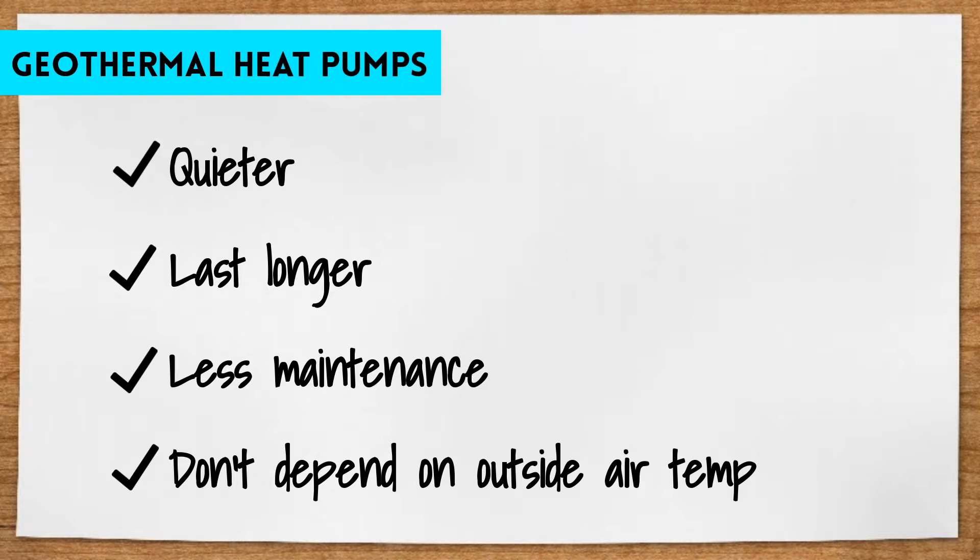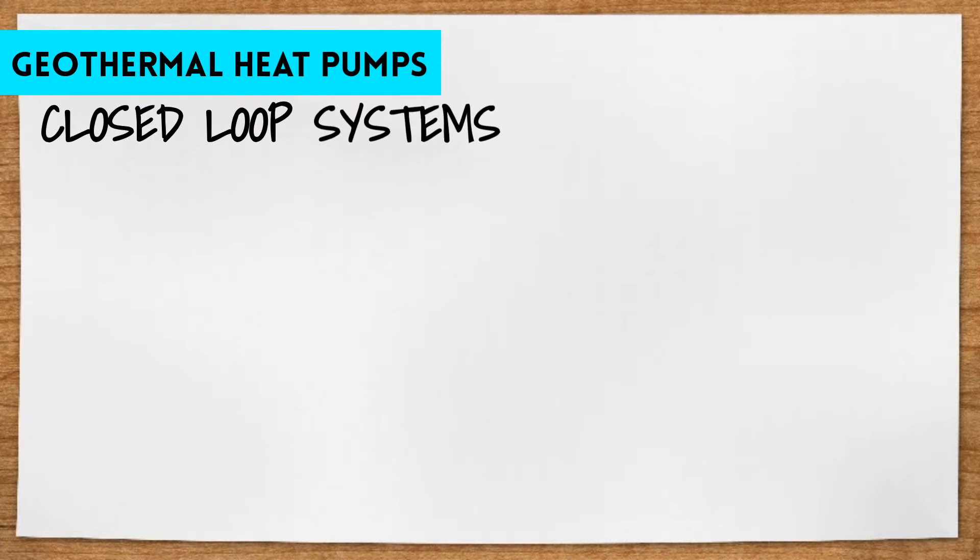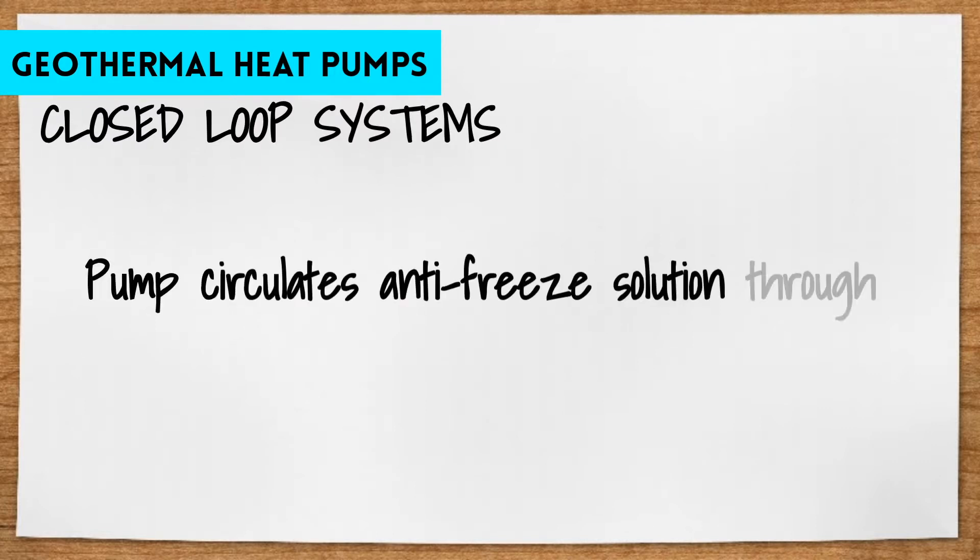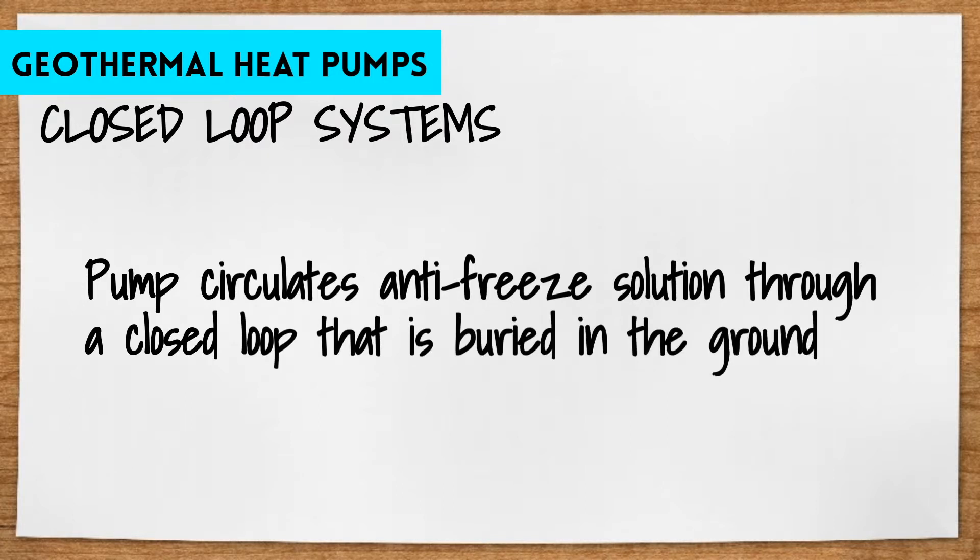There are four major types of geothermal heat pumps to know about. The first three are closed loop systems, meaning the heat pump circulates an antifreeze solution through a closed loop that's buried in the ground or submerged in water. The heat exchanger transfers heat between the refrigerant in the heat pump and the antifreeze solution in the closed loop.